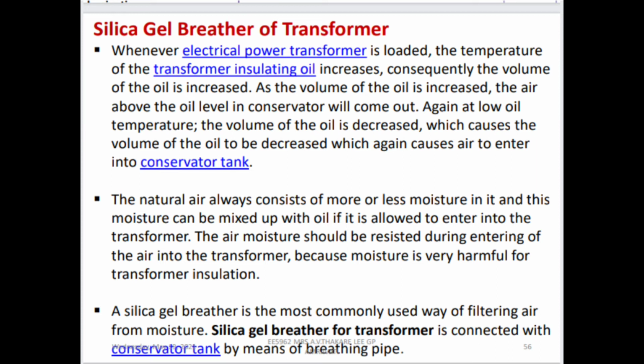So whenever an electrical power transformer is loaded, the temperature of the transformer insulating oil increases. Consequently, the volume of the oil increases. As the volume of the oil increases, the air above the oil level in the conservator will come out. Again, at low oil temperature, the volume of the oil decreases, which causes air to enter into the conservator tank. The natural air always contains more or less moisture, and this moisture can mix with the oil. If it is allowed to enter into the transformer, the air moisture should be removed during entering of the air into the transformer, because moisture is very harmful for the transformer insulation.